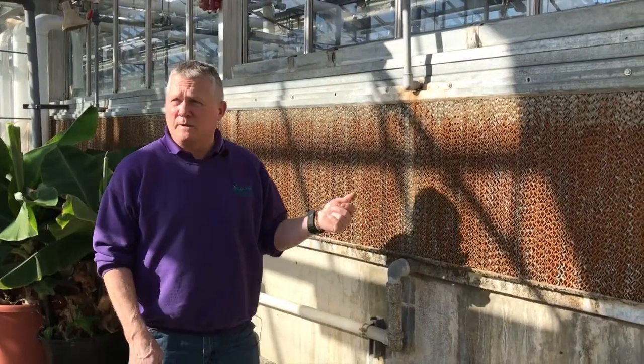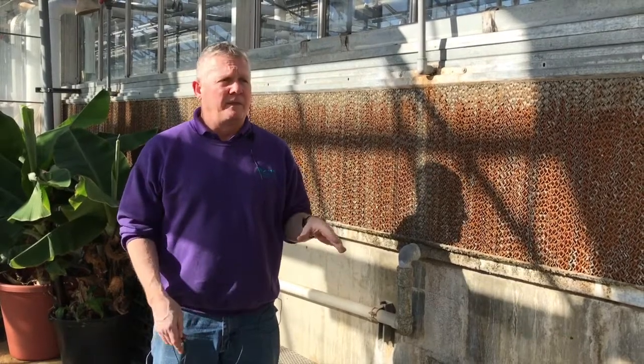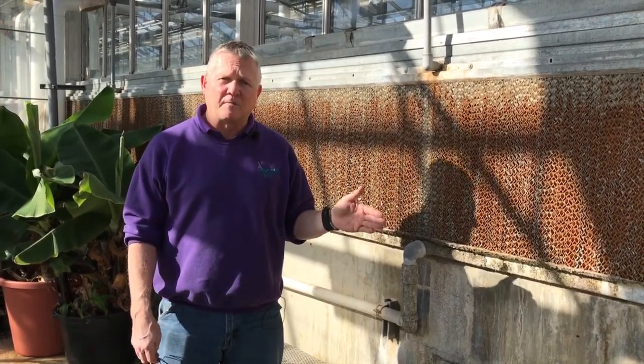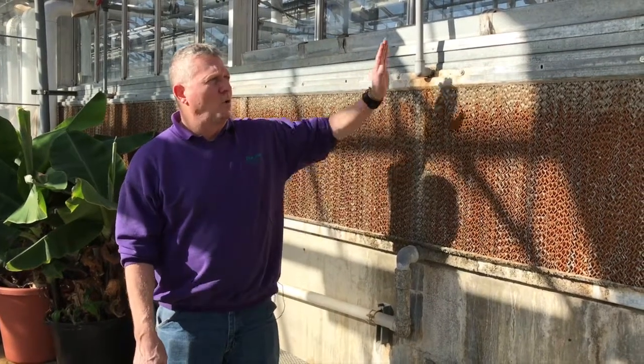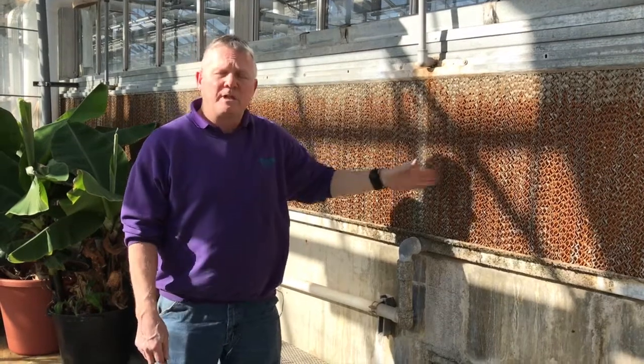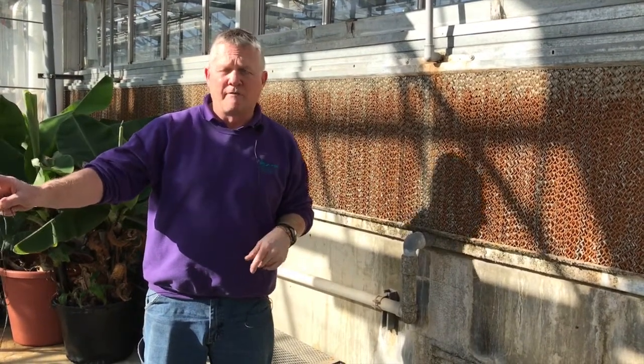Because the sun is shining today, with the greenhouses being glass enclosed, the temperatures become really warm inside here. So we've turned the fans off, but normally the fans would be running. The cooling system within our greenhouses is a pad and fan system. So what happens is cool air is drawn through the center vents in the hallway, through these pads, and then exhausted out the side walls through those large fans.